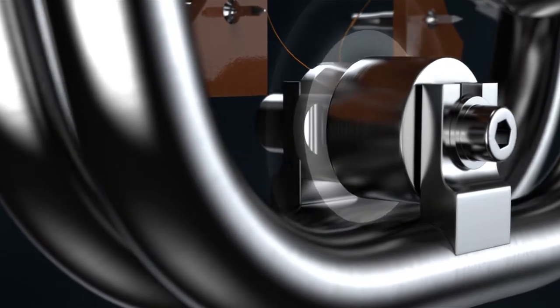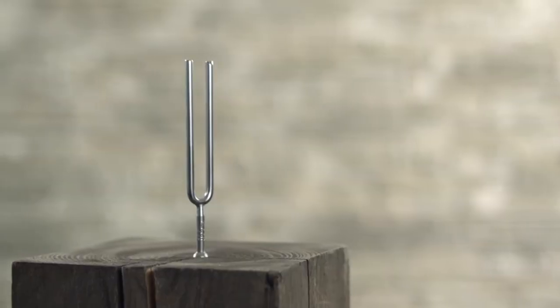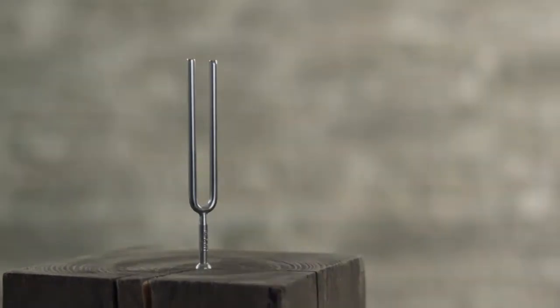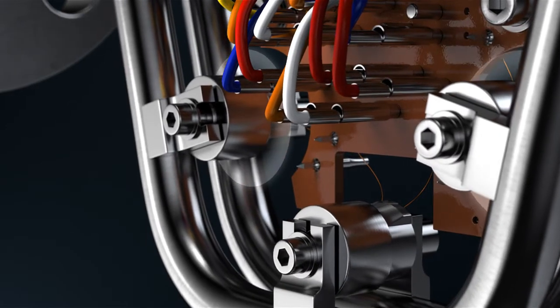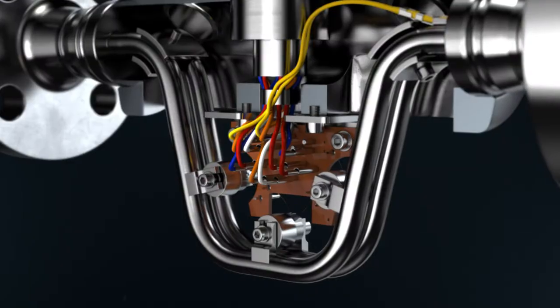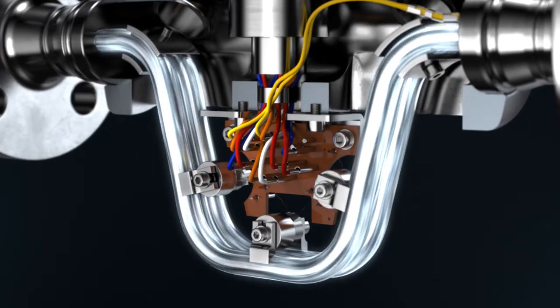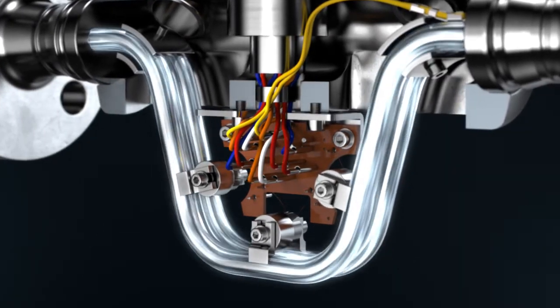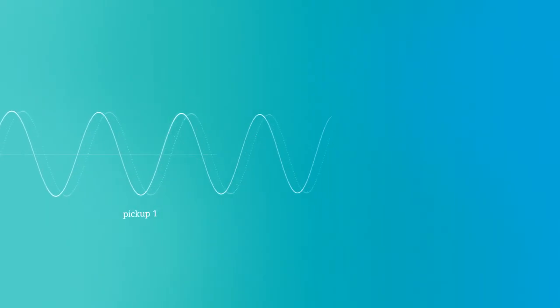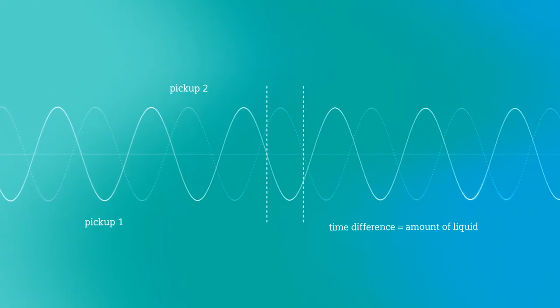The tubes oscillate with a resonance frequency, similar to a tuning fork. The oscillation is measured precisely by two pickups at the inlet and outlet sections. If liquids or gases now flow through the tubes, a phase shift occurs, as with a water hose. The pickups measure the spatial and temporal displacement.